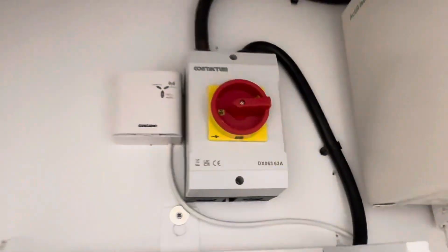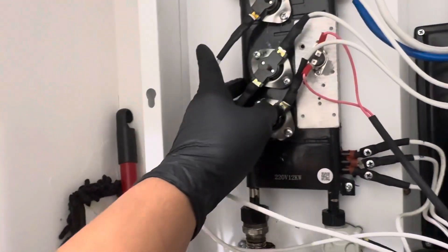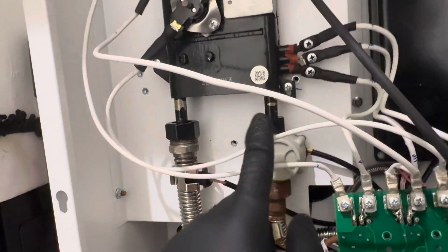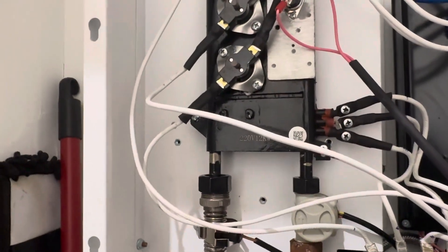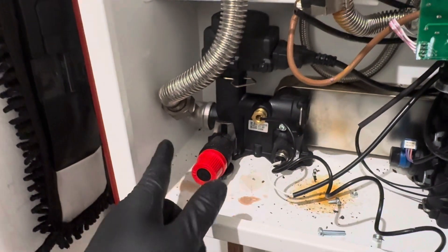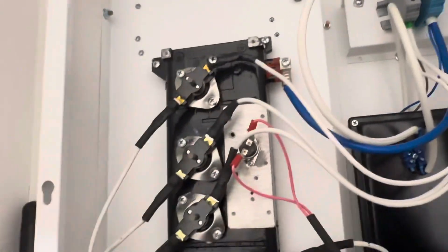Not done one of these before, so it's going to be an exciting experience. I'll remove the panel and the front case. Electrics is isolated and this is what we're replacing — this element. We're going to stick the stats onto the new one, the two connections, and the PCB too, because it is all making it blow. It should just be a case of pulling the PRV or draining the boiler, doing these two connections and these screws, and just rebuilding.